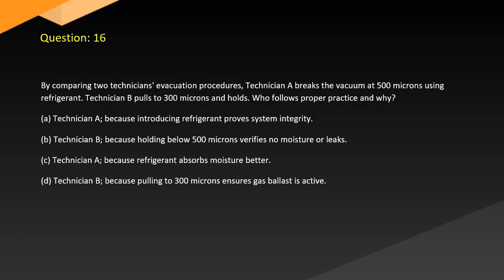Question 16. By comparing two technicians' evacuation procedures, Technician A breaks the vacuum at 500 microns using refrigerant. Technician B pulls to 300 microns and holds. Who follows proper practice and why? A. Technician A, because introducing refrigerant proves system integrity. B. Technician B, because holding below 500 microns verifies no moisture or leaks. C. Technician A, because refrigerant absorbs moisture better. D. Technician B, because pulling to 300 microns ensures gas ballast is active.